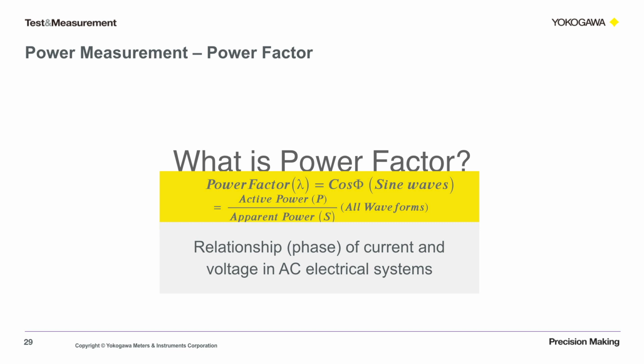Power factor, often indicated by the symbol lambda, equals the cosine of phi for sine waves, also called the displacement power factor. In complex waveforms, power factor equals active power divided by apparent power. This is called the true power factor. Power factor defines the phase angle between the current and voltage waveforms, where I and V are the magnitude of RMS values of the voltage and current. And it's generally expressed as either a decimal value, for example 0.95, or as a percentage, 95%. It's also unitless.